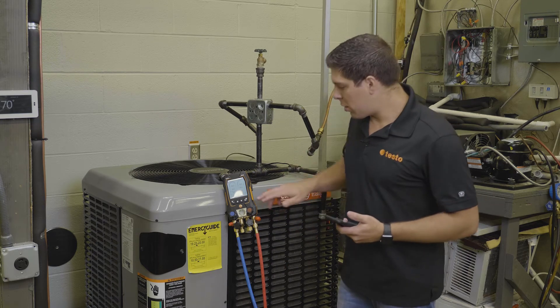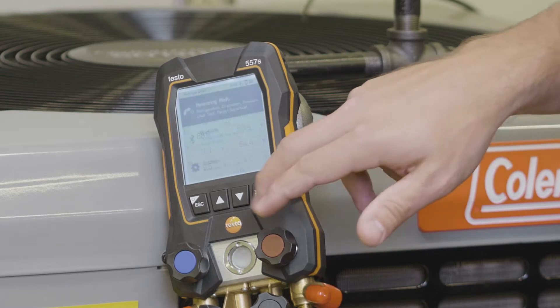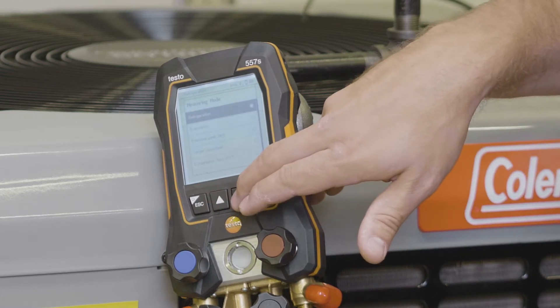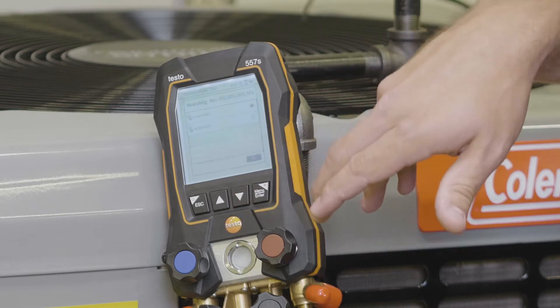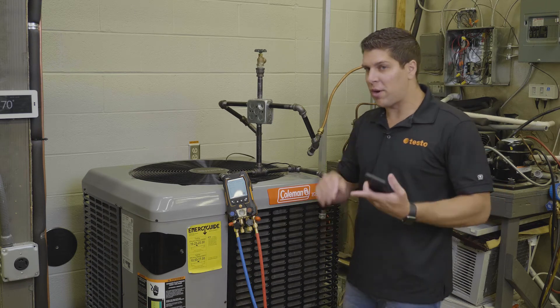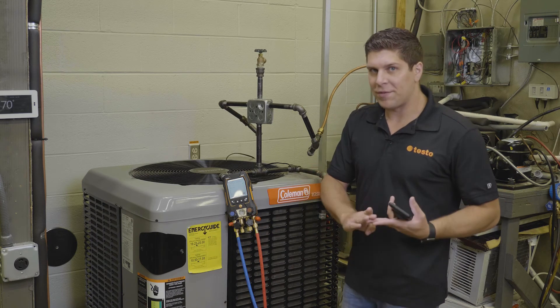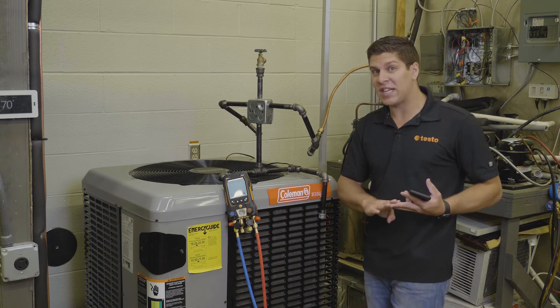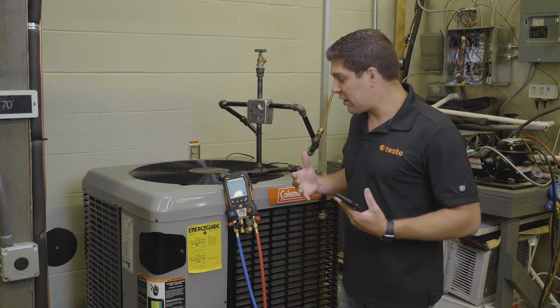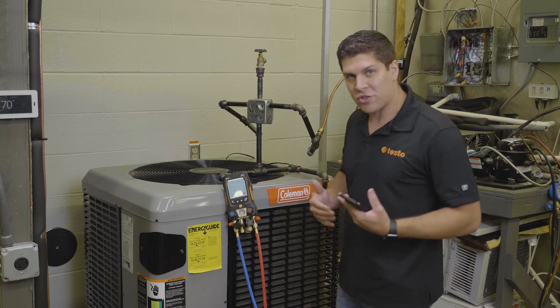We're going to go back into our menu, hit measuring modes, and go down to the pressure leak test. The pressure leak test does allow for temperature compensation, so you can use smart probes — whether you have a 905i, a 115i, or the new 915i thermocouple type K smart probe — you have the ability to use those to get your temperature compensation.